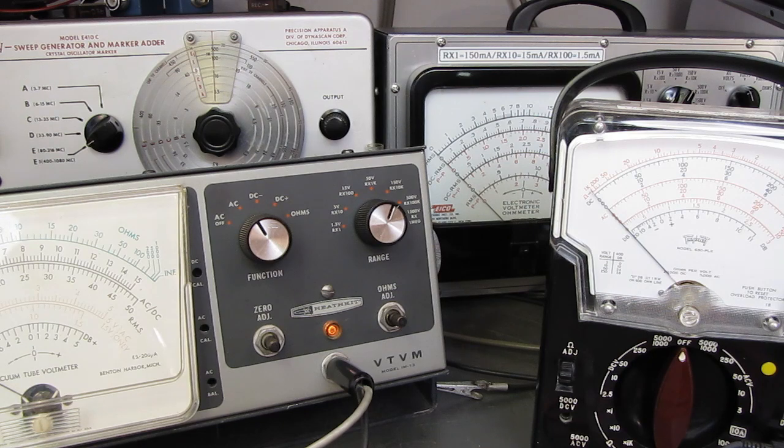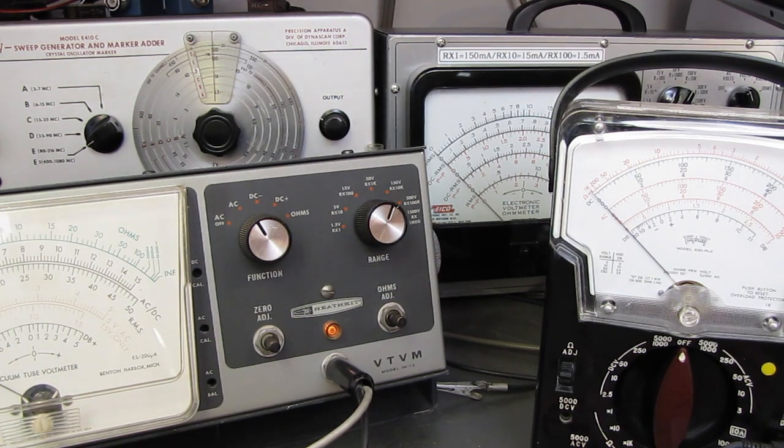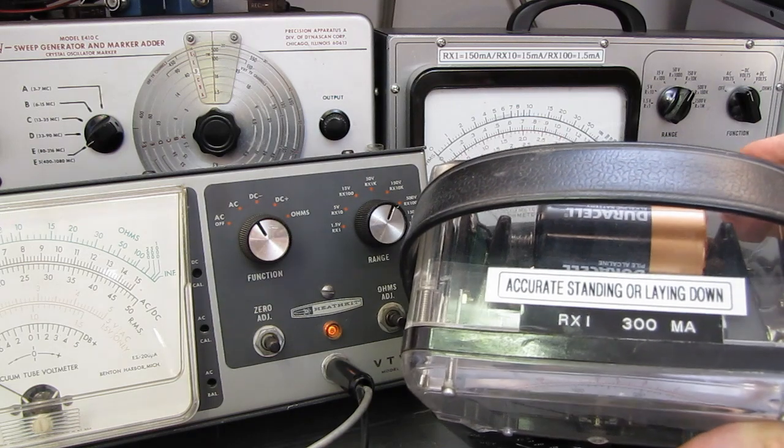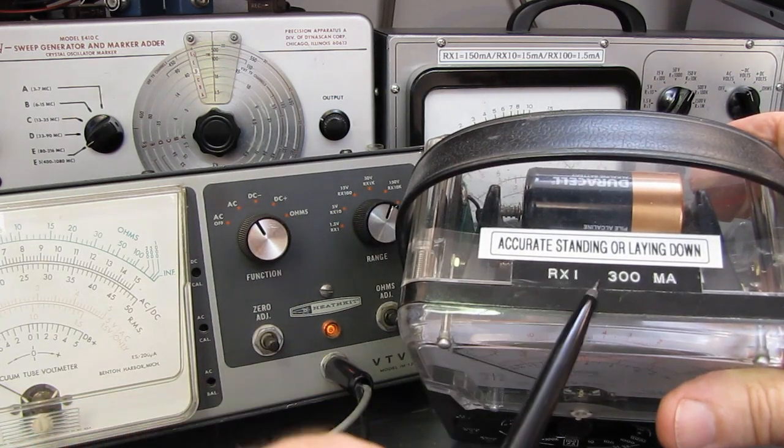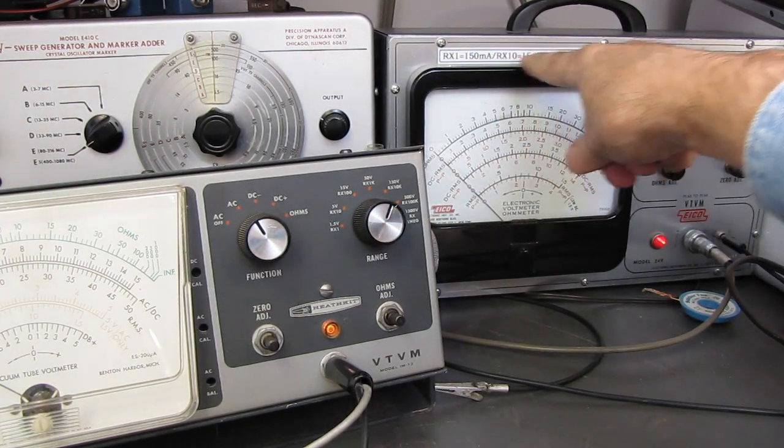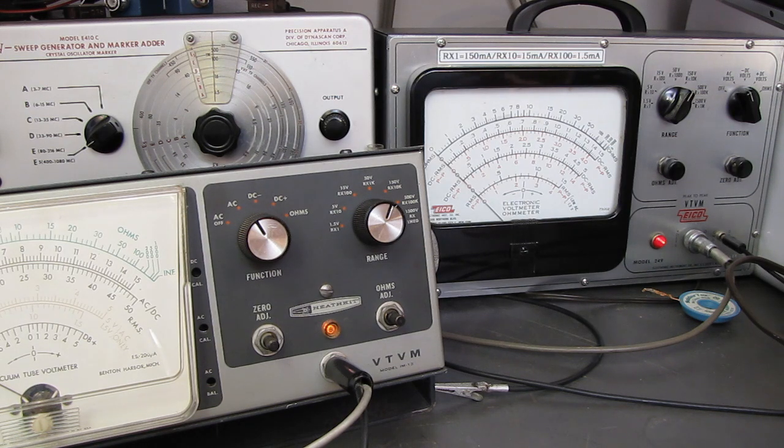But wait, there's more. I promise this is it. This is something I meant to do and I spaced it. I get asked all the time. Why on top of my meters I have this R times 1 300 milliamps. R times 1 150 times 10 15 and so on. You should characterize your meters. The reason being, it's not uncommon today to see fuses that are a tenth of an amp. 150 milliamps.